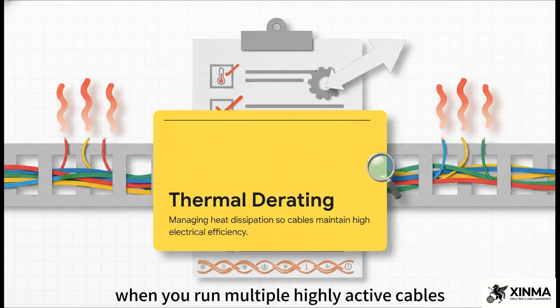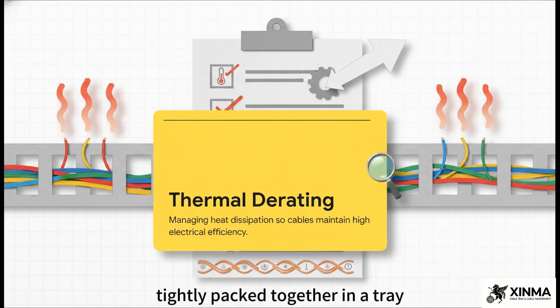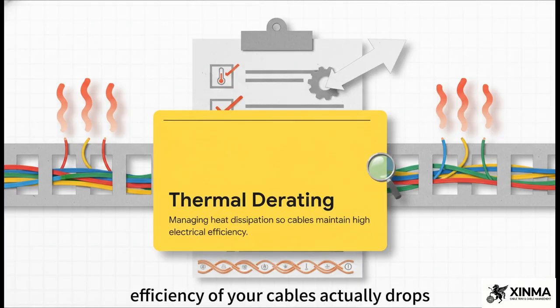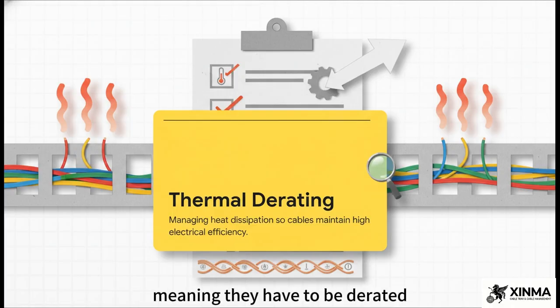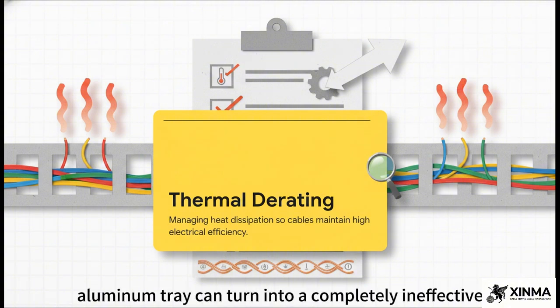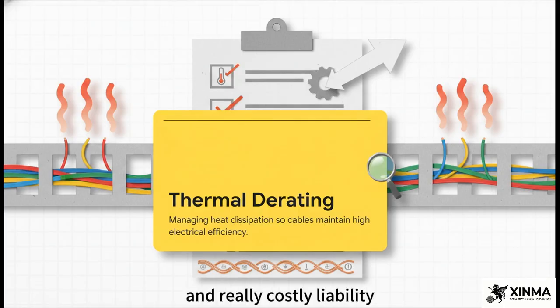Think about it. When you run multiple highly active cables tightly packed together in a tray, they generate a lot of heat. If that heat can't escape properly, the electrical efficiency of your cables actually drops, meaning they have to be derated. If you overlook critical nuances like this or skip proper electrical bonding, even the highest quality, top-tier aluminum tray can turn into a completely ineffective and really costly liability.